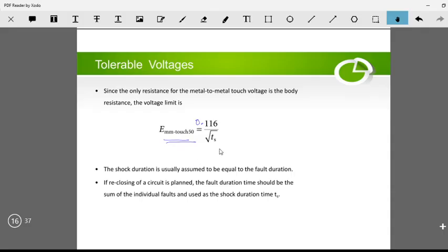This shock duration TS is usually assumed to be equal to the fault duration. Unless the fault is cleared by some other means, like a circuit breaker, the current will flow through the body. So TS is assumed to be equal to the fault duration.